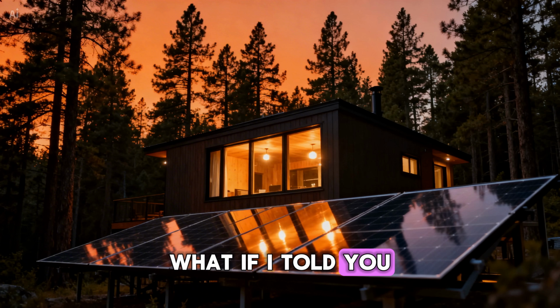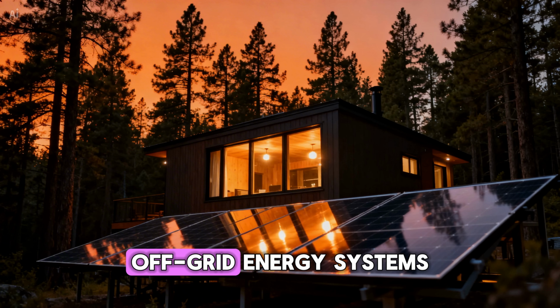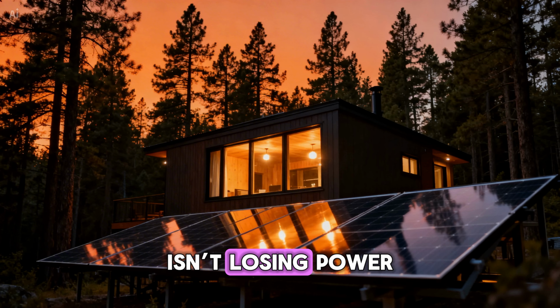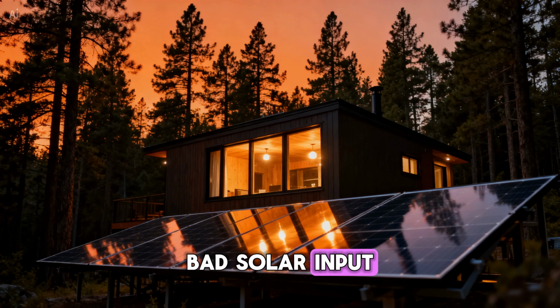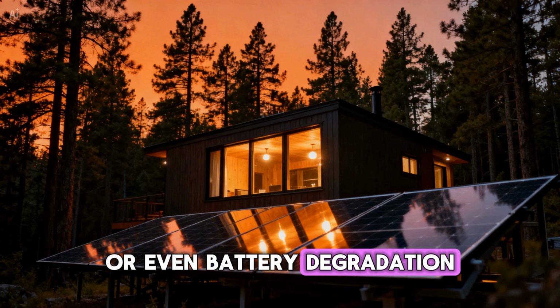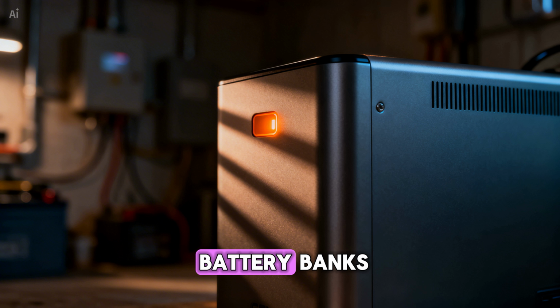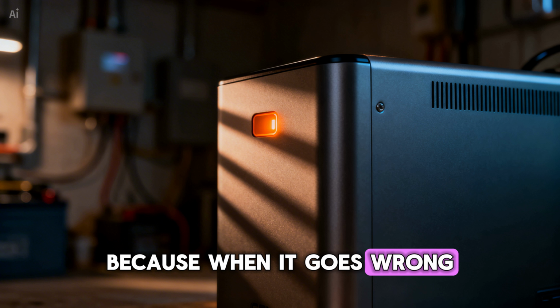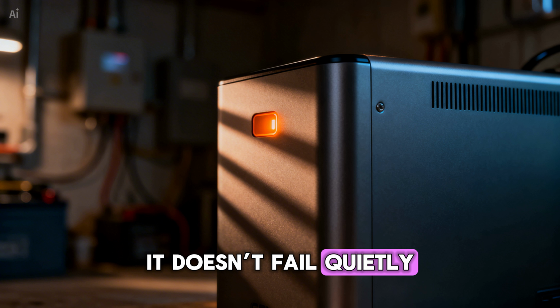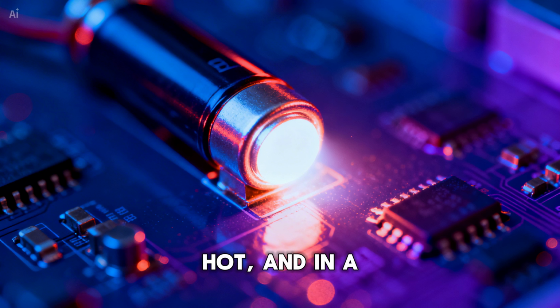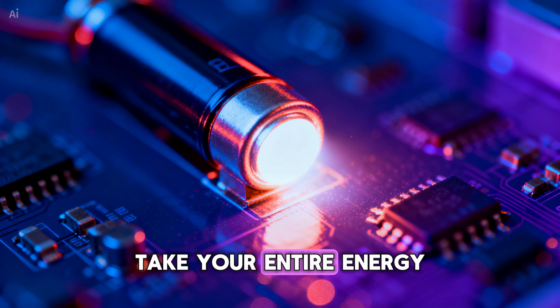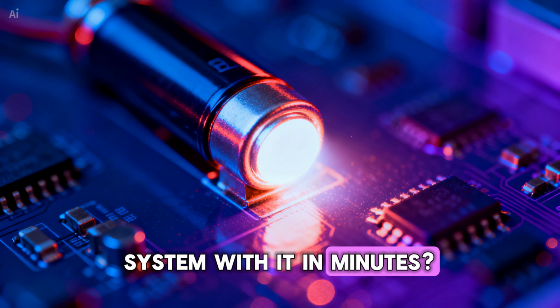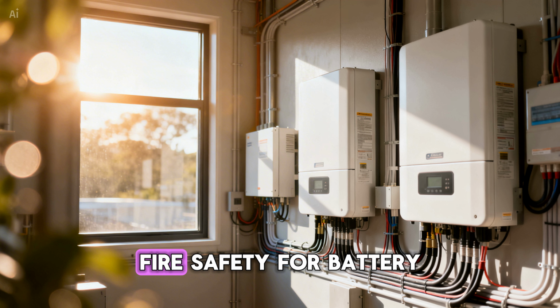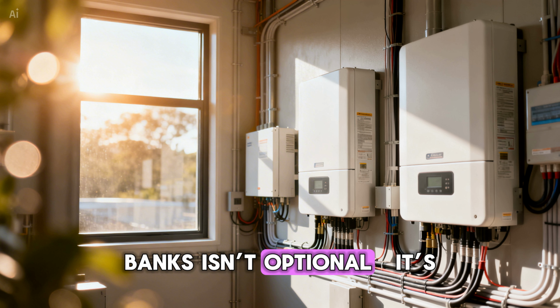What if I told you the biggest hidden risk in off-grid energy systems isn't losing power, bad solar input, or even battery degradation? It's fire safety in battery banks, because when it goes wrong, it doesn't fail quietly. It fails fast, hot, and in a way that can take your entire energy system with it in minutes. That's why understanding fire safety for battery banks isn't optional.